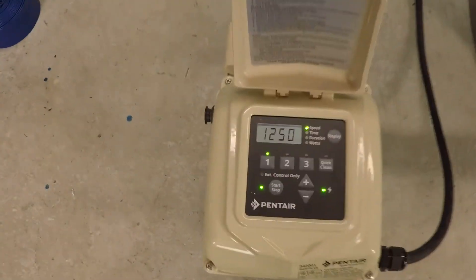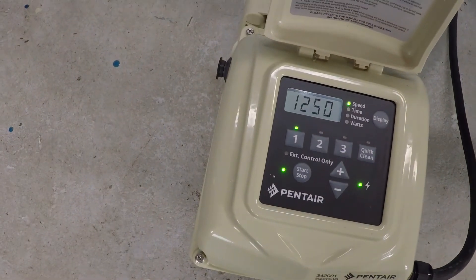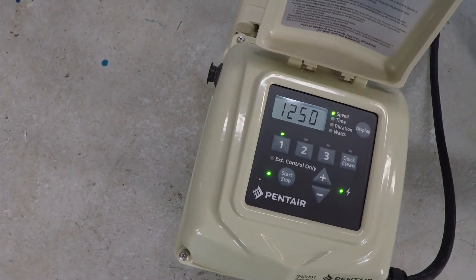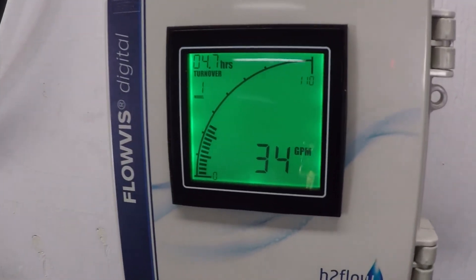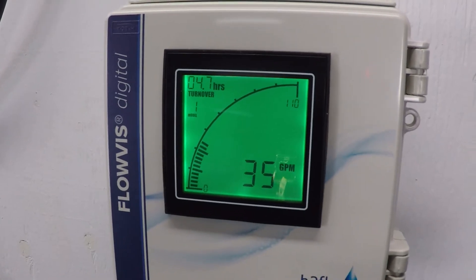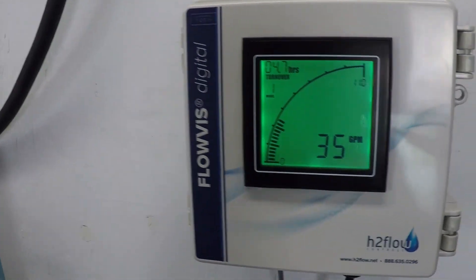What I was able to do was dial in the RPM of my pump — this is the Pentair SuperFlo variable speed, 1.5 horsepower. It took 1,250 RPM in order for me to achieve that 35 gallons per minute of flow that was being requested. Again, this number is different in every pool, but I just wanted to give you some sort of real-world number.